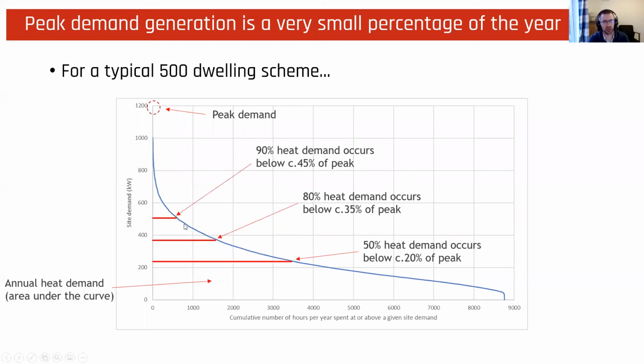And what this graph is showing is the amount of time spent at different demand during the year. So for 90% of the year, we actually typically see heat networks sitting below 50, actually below 45% of the peak demand. So this is for a typical 500 dwelling scheme where the peak demand is around 1.2 megawatts, 1200 kilowatts. And actually for 90% of the year, 90% of the heat demand is occurring below 500 kilowatts in this example. Moving that further down the curve, 80% of that heat demand is occurring below 35% of peak, and 50% is occurring below 20% of peak.